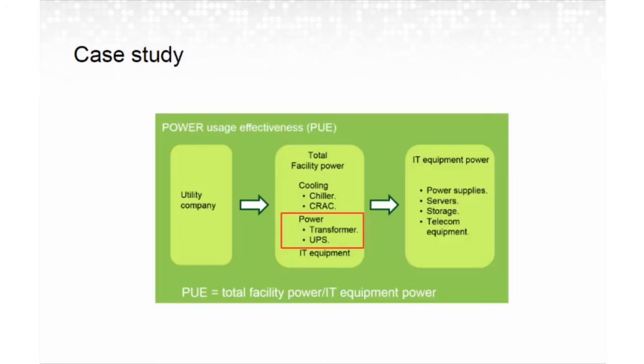One thing you'll see in the results is a mention of PUE, or power usage effectiveness. This is a data center measuring point to see how efficient your systems are. Basically, it looks at the total power compared to the power being utilized by the equipment. So in an ideal world, the PUE would be one, so every watt going into the building is being directly used by the equipment.